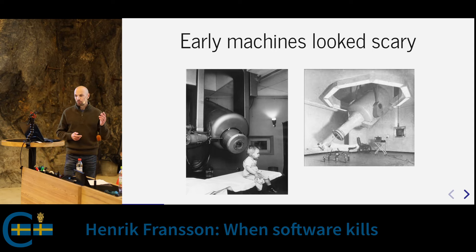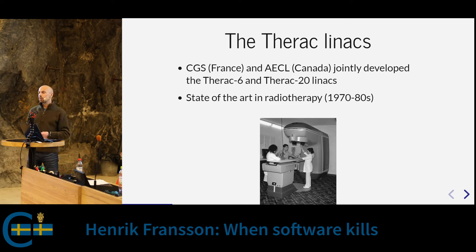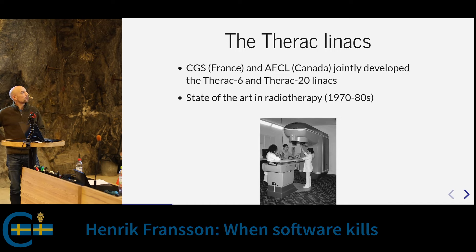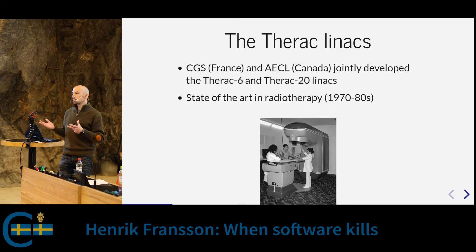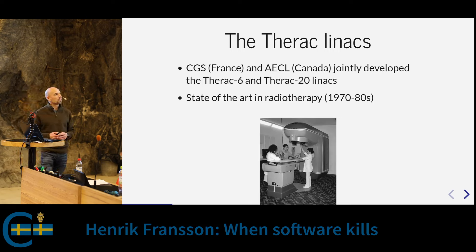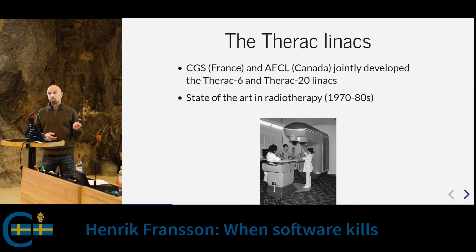That picture is from the 1950s and the first ever medical use of a linear accelerator. Going back to the Therac line of devices: in the 1970s, two companies from France and Canada did some joint development on these linacs. The first two models were called the Therac-6 and Therac-20, where the numbers refer to the megaelectronvolt energy of the X-ray beam. These were really the state of the art in the 1970s — the best radiotherapy machines you could buy — and already cost multiple millions of dollars each.